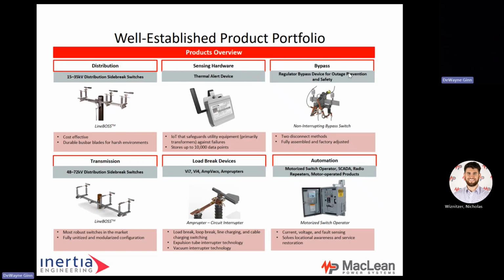This is our portfolio. Distribution products from 15 to 35 kV. So they're very cost effective, and again very robust for harsh environments as well. Transmission switches from 48 kV to 72 kV. Again, the same thing. All of our switches are unitized, so they go up very easily. They're factory adjusted, so consequently they're not going to have to be adjusted when they get to the field.